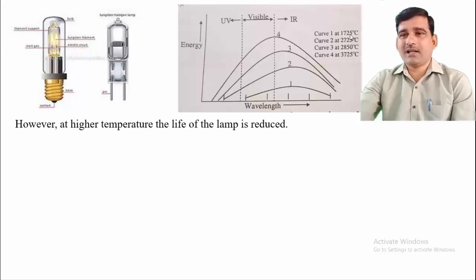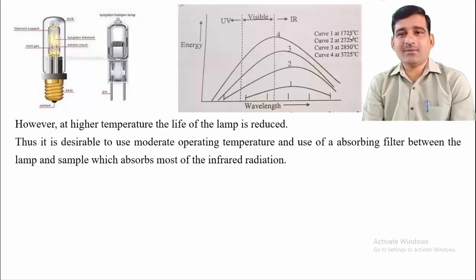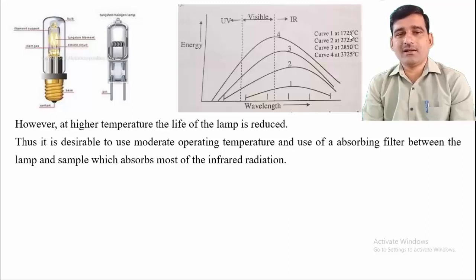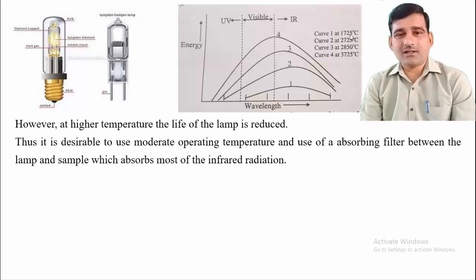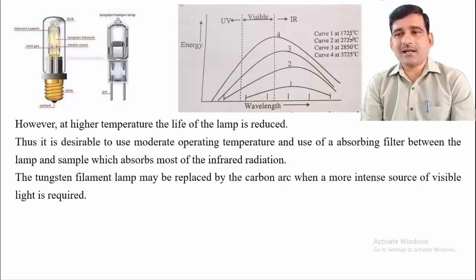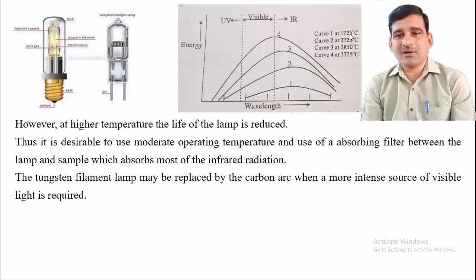An absorbing filter placed between the lamp and the sample can absorb most of the near-infrared radiation, transmitting only the visible-region light. The tungsten filament lamp may also be replaced by a carbon arc lamp when a more intense source of visible light is required. The carbon arc lamp produces an arc between two rods in a glass bulb, giving more intense light in the visible region.